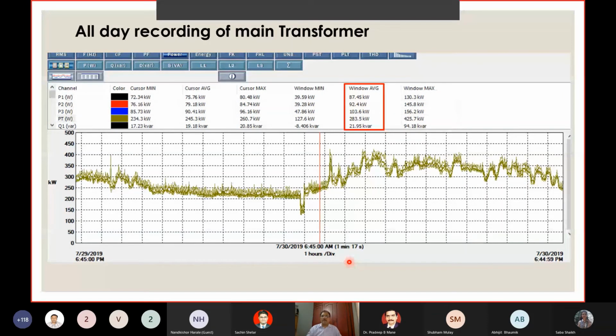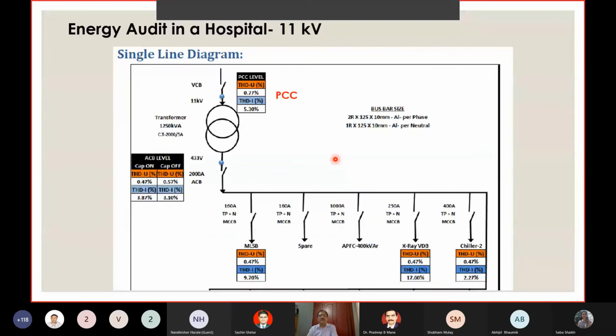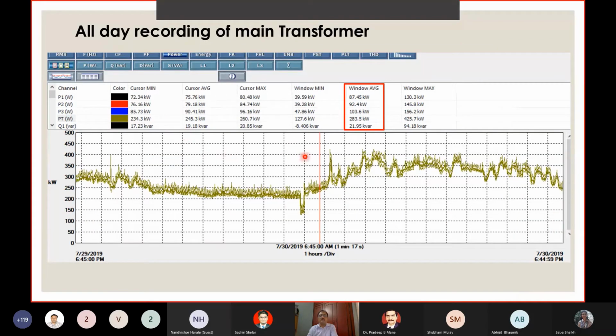This is a full-day recording using a power analyzer, from 6:45 p.m. to next day 6:45 p.m. This is the pattern of the kilowatt load average. As you can see here, during the nights it is low, during the daytime it is high. So this is approximately 283.5 kilowatt. If you remember, it's a 500 kVA sanctioned demand for this industry. The transformer is 630 kVA, 11/0.433 kV. So as you can see here, this is the finding that we have with this slide.